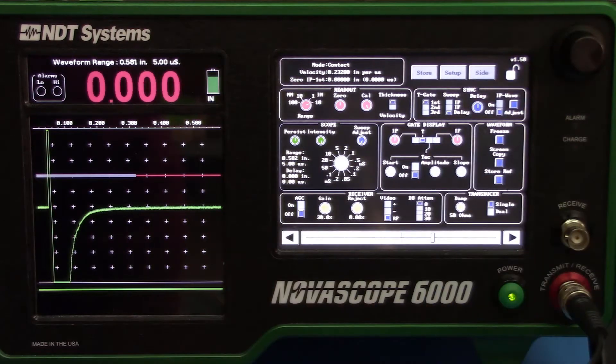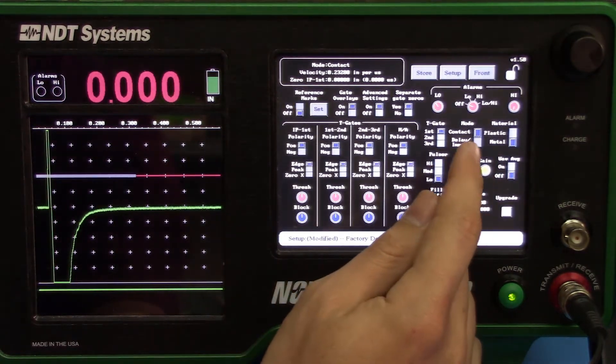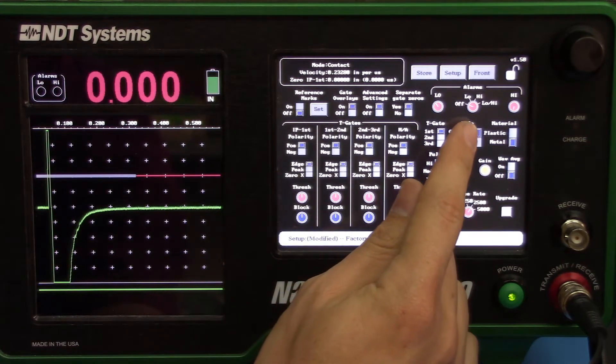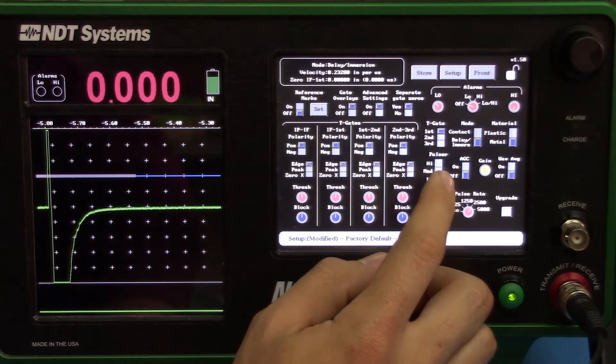Go to the Range Indicator and turn it so that we have a maximum of a little bit more than 0.5. Go to the Side again. Make sure we're on Delay/Immersion Mode. Set the Pulser to High, since wax is very attenuative.